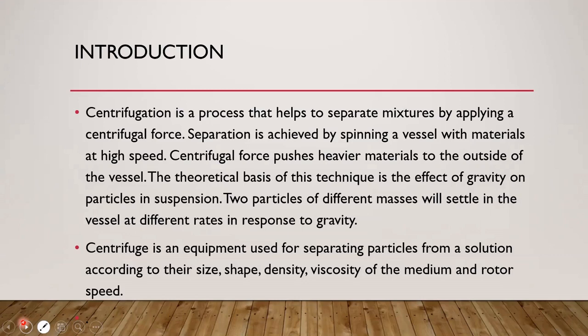The centrifugal force pushes the heavier materials to the outside of the vessel. The theoretical basis of this technique is the effect of gravity on particles in suspension — two particles of different masses will settle in the vessel at different rates in response to gravity. Heavier particles will settle first and lighter particles will settle later. A centrifuge is a device or equipment used for separating particles from a heterogeneous solution according to their size, shape, density, viscosity of the medium, and rotor speed. It is found in every biochemistry lab and is used for the analysis of physical properties of biomolecules, organelles, etc.